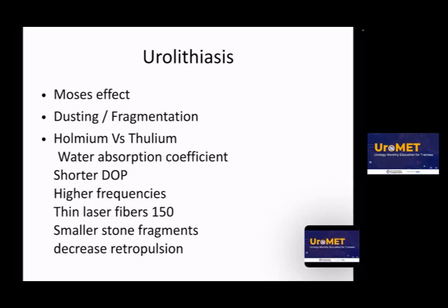And when we compare for urolithiasis treatment, holmium and thulium, the newer generation superpulsed fiber optic thulium lasers are more effective. Compared to the water absorption coefficient, the thulium laser's coefficient is 4 times higher, and the depth of penetration is very short in thulium lasers, around 0.2 millimeter.